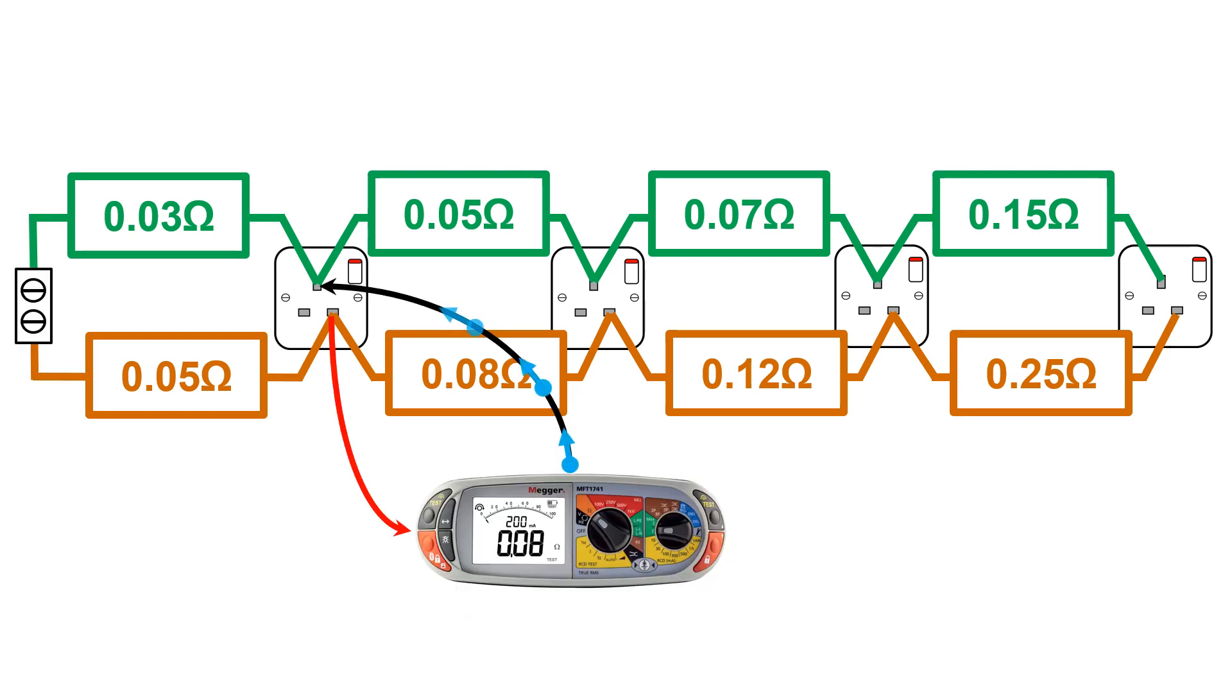To test R1 and R2 together for ease and to save time, we connect the two conductors together into a connector block at the supply end of the cable and then test between R1 and R2 at each point, operating the switches on accessories as we go to proof functional switching and moving downstream in the circuit until we find the highest resistance. This may or may not be the furthest point because we should never assume for obvious reasons, like a faulty socket, for example.